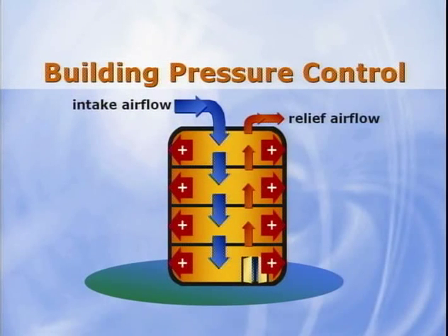Maintaining a desired building pressure in the face of continuously changing supply and exhaust airflow requires an automated fan and damper control scheme and is paramount to proper building operation and comfort. For rooftop VAV systems with airside economizers, the quantity of relief air is controlled to maintain the space pressure. There are two configurations of VAV relief air systems, the central return fan and the central relief fan. Controlling space pressure involves coordination of these rooftop fans and their dampers.